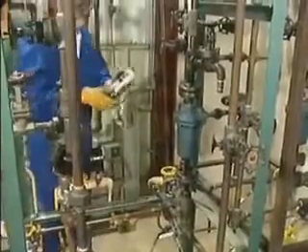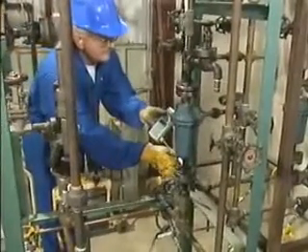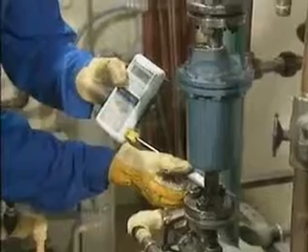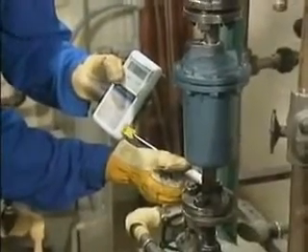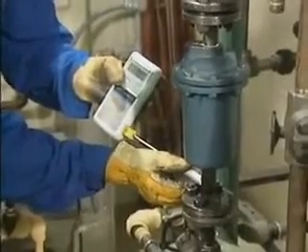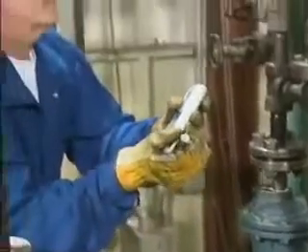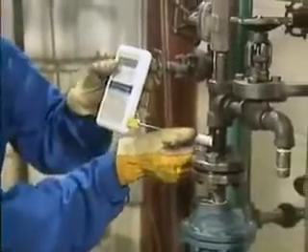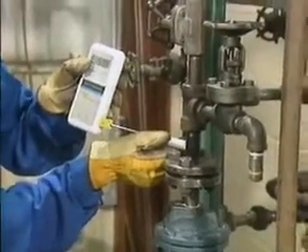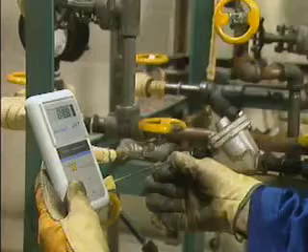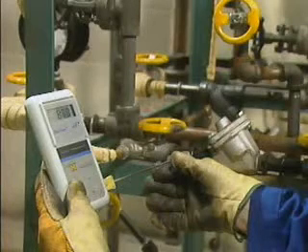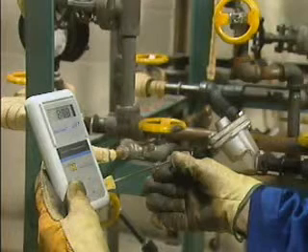A temperature inspection is usually a good starting point for a trap survey. The temperature at the trap's inlet and outlet pipes should be in the normal range for the specific trap installation. Generally, the inlet should be hotter than the outlet, but if the outlet is cold, it could indicate that the trap has failed closed. Whatever method you use for a temperature check, you must be able to interpret the meaning of the information that you obtain.